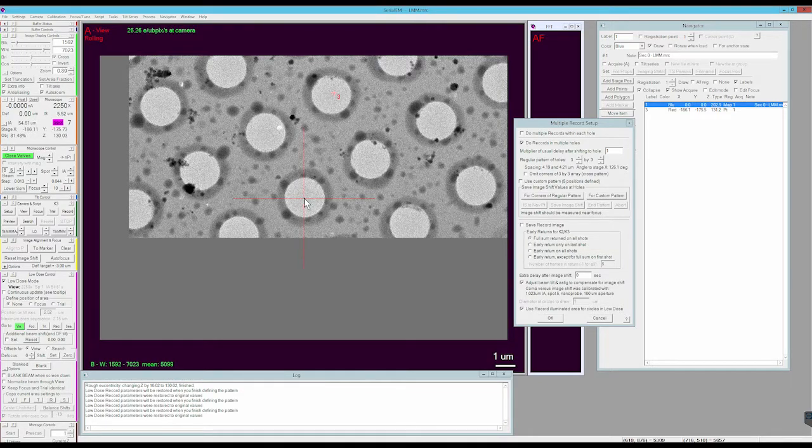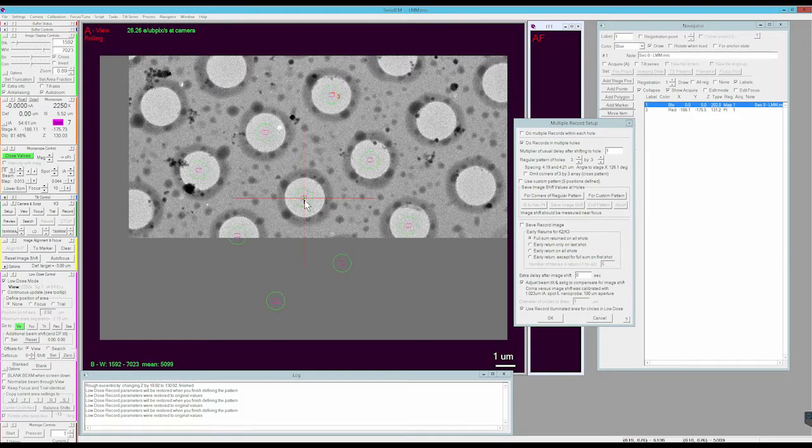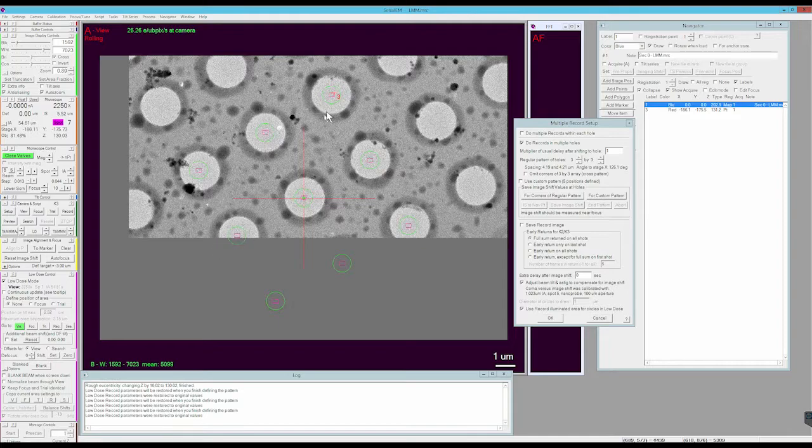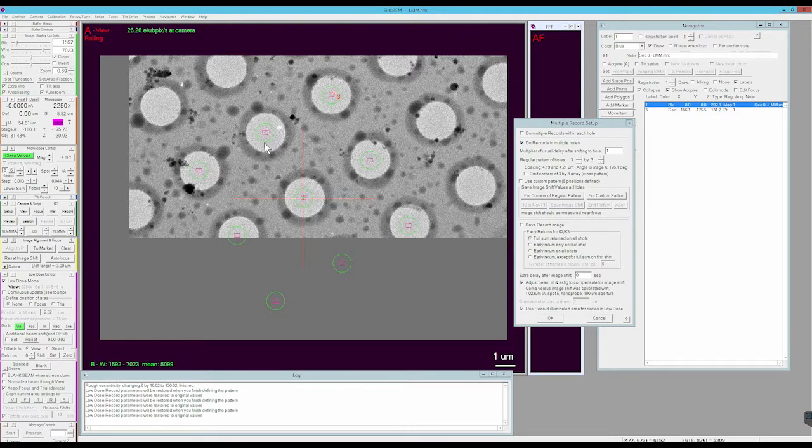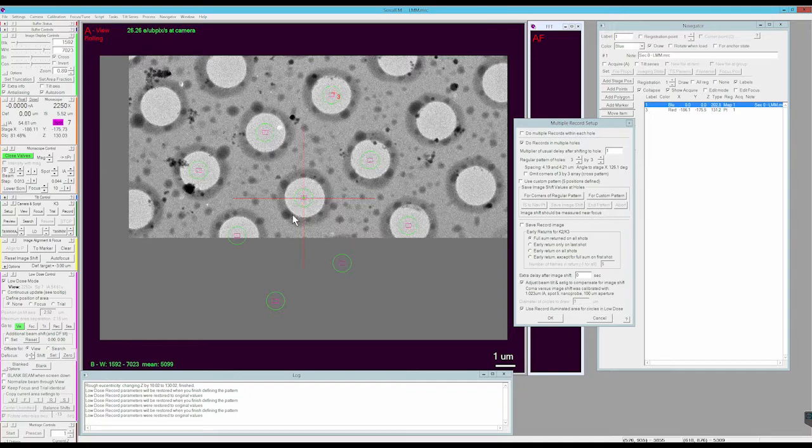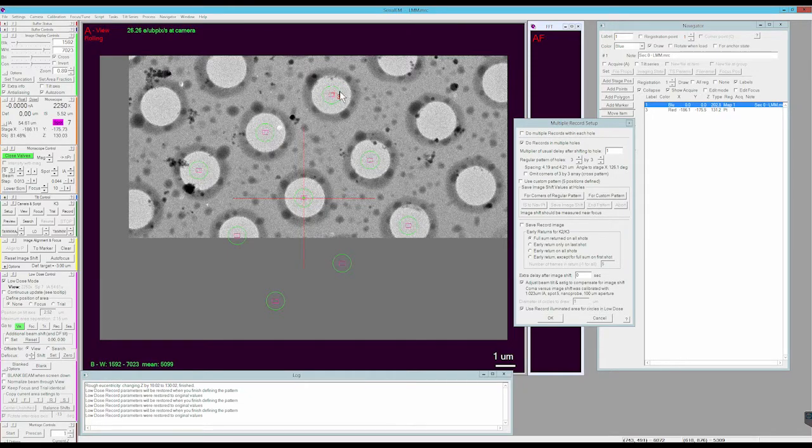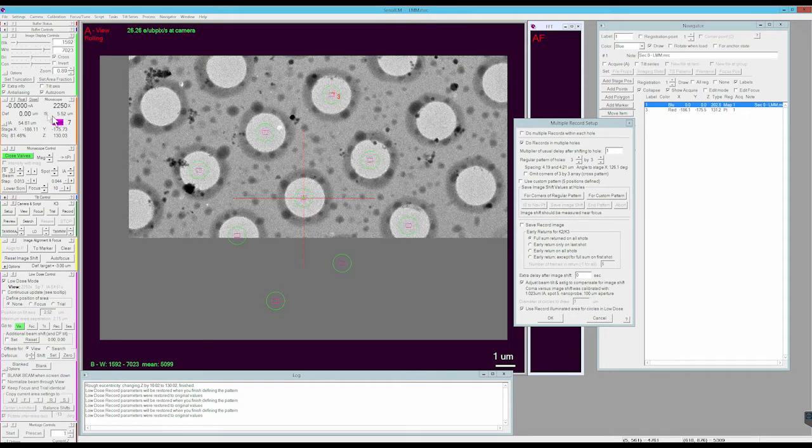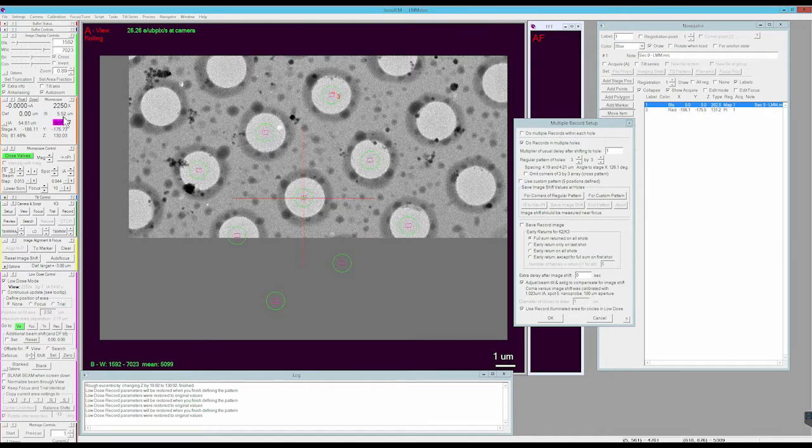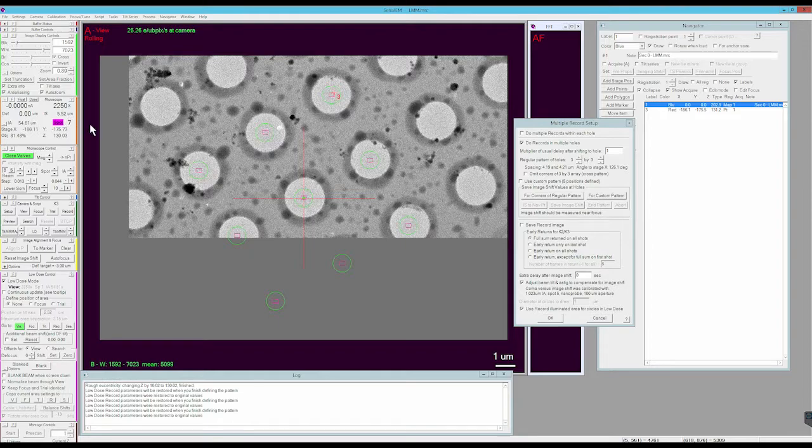If I click on the area where my crosshairs are, you'll see a 3x3 pattern displayed. This is not the hole that I started with. I started with the hole with the 3 marker on it and you'll notice that image shift is at 5.52 microns. So in order to test this or further calibrate it, we should remove the image shift.